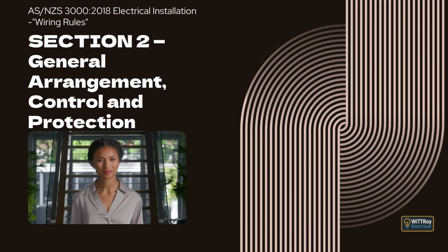Clause 2.10.3.4 Orientation and location of fuses and circuit breakers. Clause 2.10.3.4.1 Orientation of circuit breakers. If more than one circuit breaker is mounted in a row, they must all operate in the same direction so that the off and on positions are clear and consistent. You must always be able to see which position each device is in.